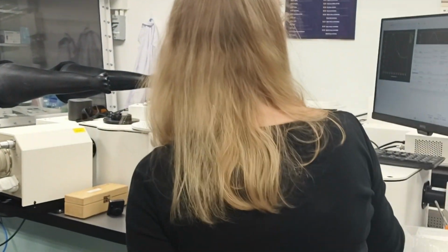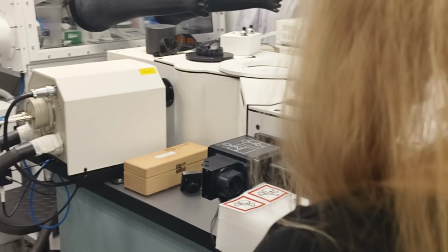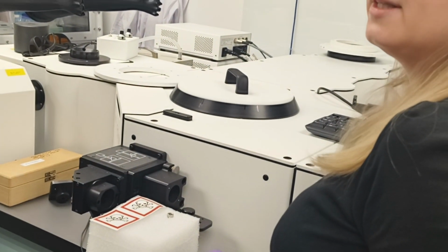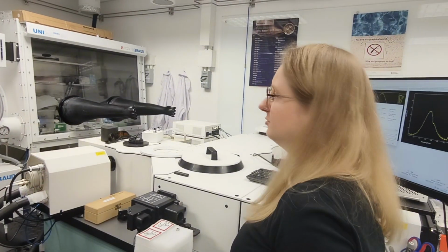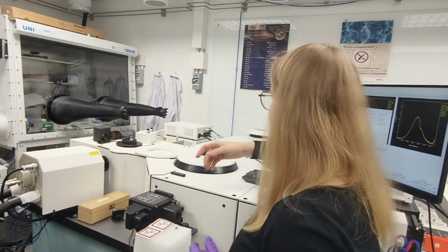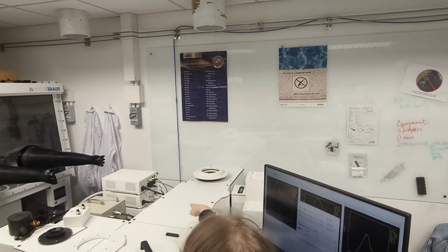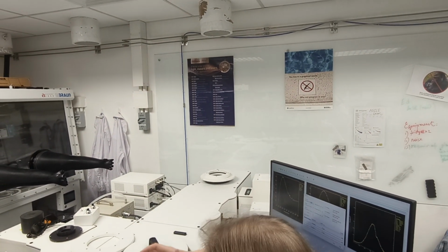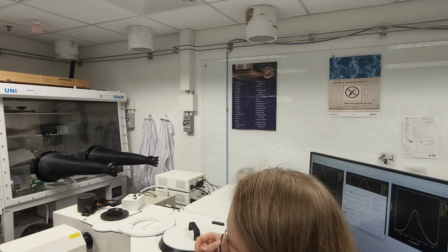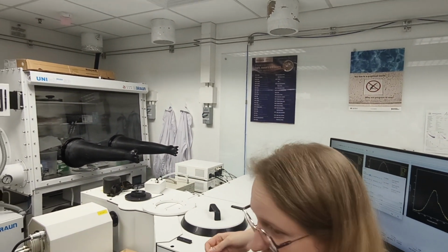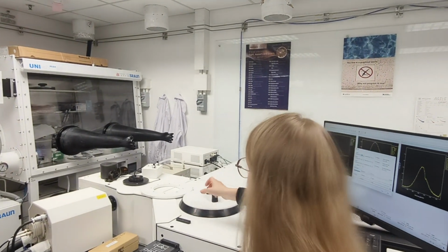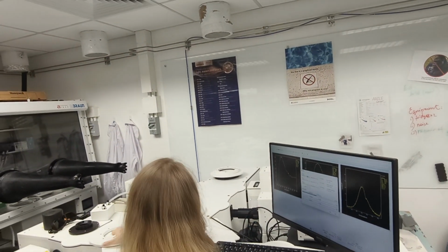Then I go to the spectrometer. This big thing we call a photoluminescence spectrometer, and it has a xenon lamp over there. It's super intense, 150 watts, so it's closed. You cannot see it by eye, it will harm your eyes. Then it has a monochromator. What is a monochromator? It's a system which defines certain wavelengths. Mono means single, and chromic means of color.